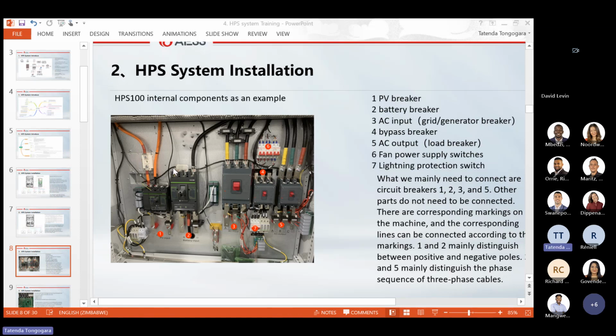Okay, this is how the internal components of our HPS look like. So point one, that's your PV breaker. That's where you connect your PV cables, the battery. And then we have AC input. So AC input, if it's an HPS 100, you can send two times the size of your HPS capacity. So if it's HPS 50, you can get 100 kilowatt from HPS 50 on the AC input that's used to charge the battery. The other one passes through to your load.